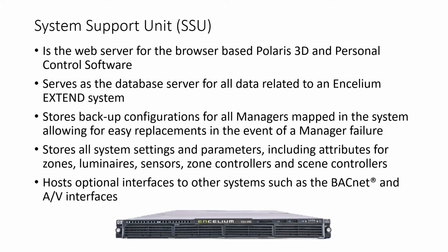It stores all system settings and the configurations of all of the managers. If manager hardware needs to be replaced, the new manager receives its configuration from the SSU. Note that once the managers are configured, they run independently. If the SSU goes down, the system continues to operate without it. In addition, optional building automation system interfaces, such as BACnet and an AV interface, are available as add-on functions of the SSU. Each Extend system requires one SSU. The server may be an Encelium or customer-supplied dedicated physical, or customer-supplied virtual or cloud-based solution.